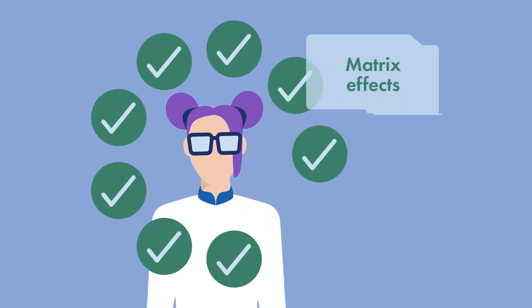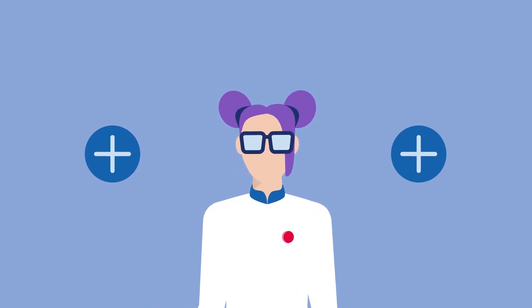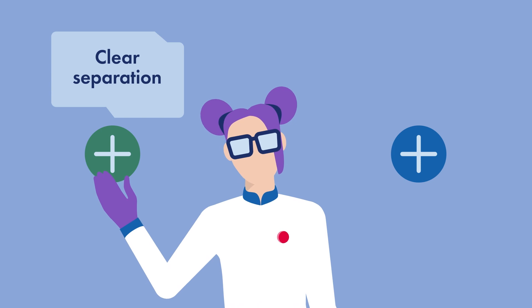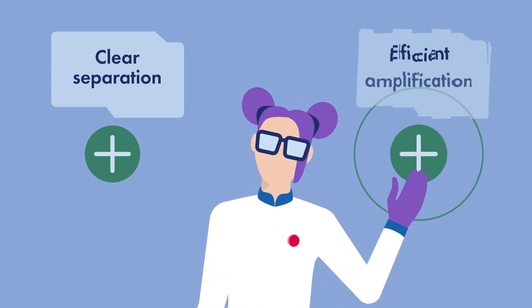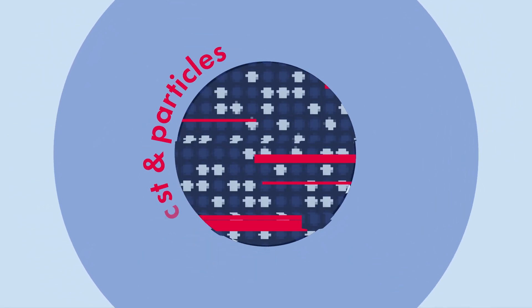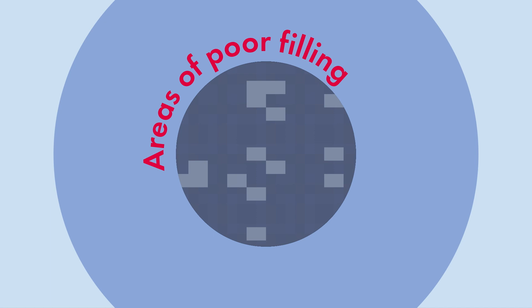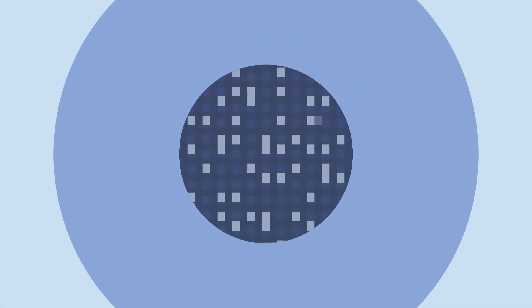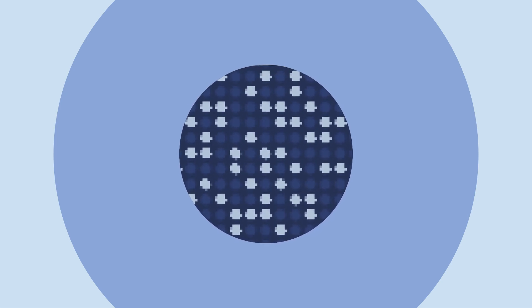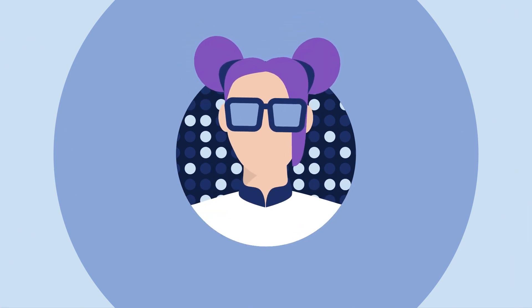Matrix effects are some of the parameters that, when properly checked, can influence positive outcomes such as clear separation between positive and negative partitions and efficient amplification. To ensure accurate analysis based on valid partitions, artifacts such as dust and other particles, low amplification areas, and areas of poor filling or imaging — if any — that could influence the result analysis are removed from the images by automatic corrections done by the software, and do not require any action on your part. Re-imaging the plate is always an option.